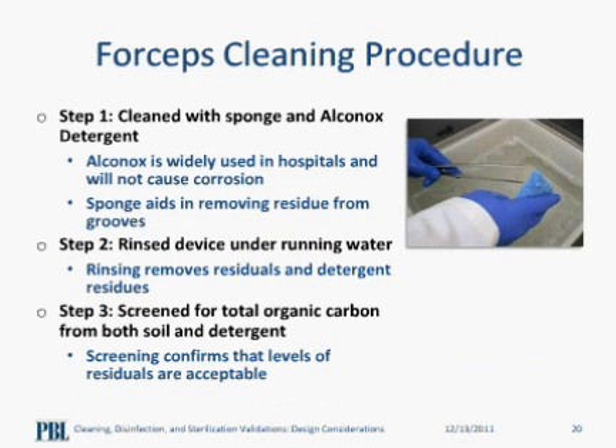After cleaning in the Alconox detergent, we rinse the forceps under running water. Not only will this help wash away loosened debris, it will also remove any remnants of the detergent. This is true of any chemicals that may be used on your device. If the rinsing is not adequate, residuals from the disinfectants can potentially be very harmful to your patient.